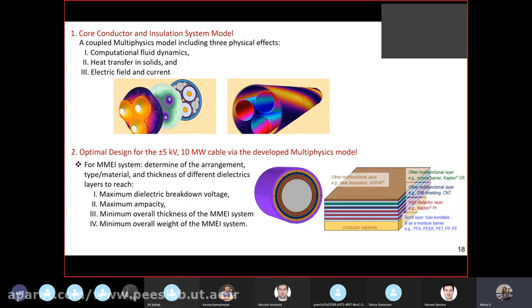This is a very complex multi-objective problem where there are many variables we take into account—for example, the type of material, the thickness of the dielectric layers, the maximum dielectric breakdown voltage of each layer and the whole layer, the maximum ampacity, the minimum overall thickness of the system, and the minimum overall weight of the system. That's a very interesting project, and it can be extended to all other electric equipment.